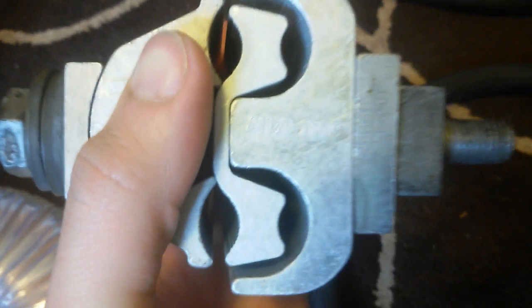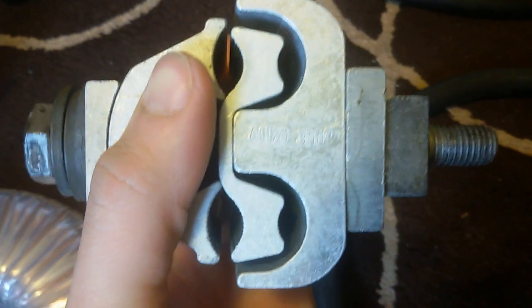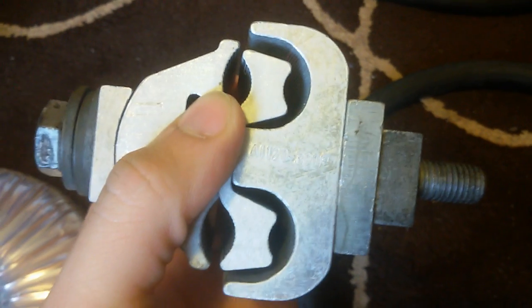Yes, this one is actually aluminium, for aluminium wire, but I just put copper in it. 300 square millimeters on the bottom one, and the top one is 120 square millimeters, so you can actually put 4 wires in this. Very good connectors, and that part here is supposed to be on the transformer bushing.